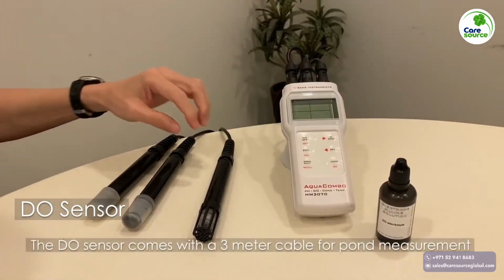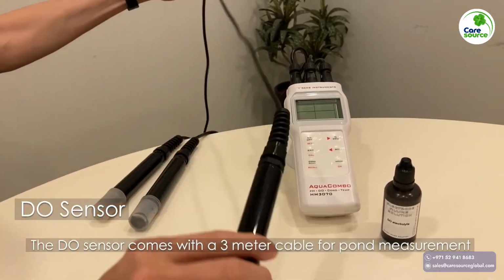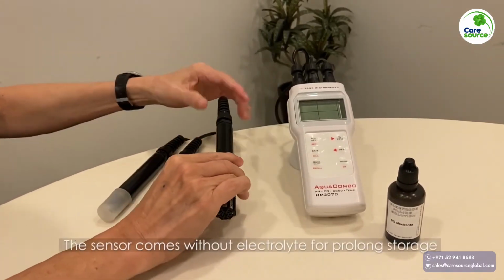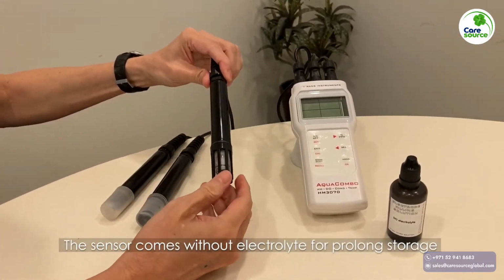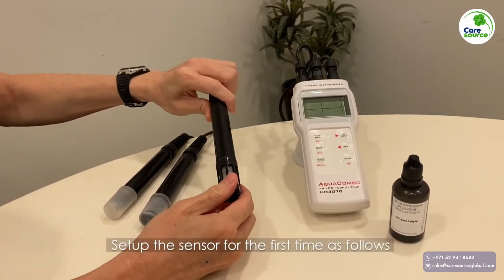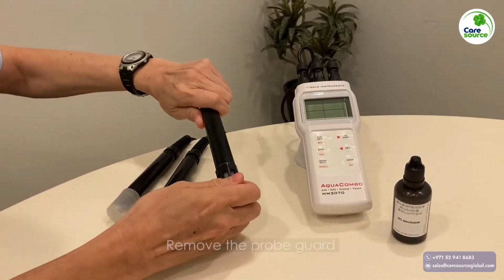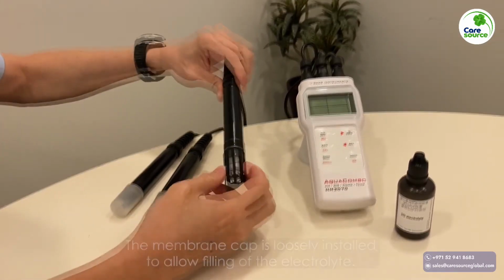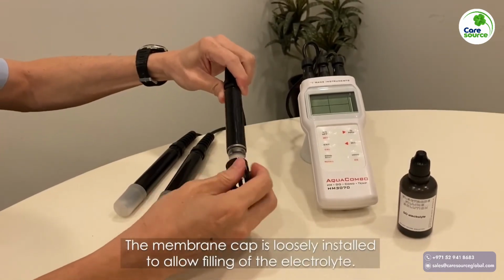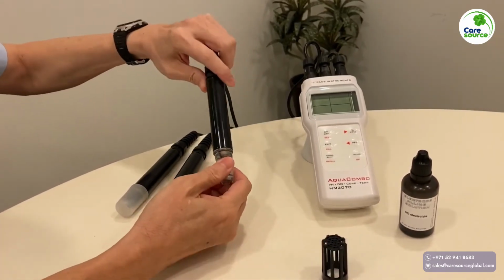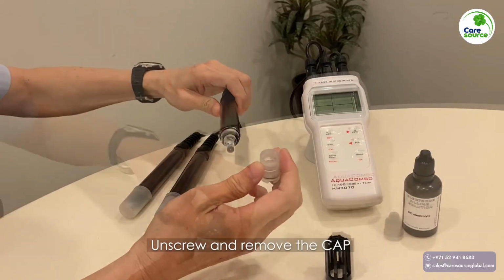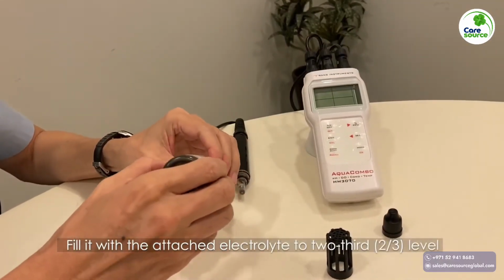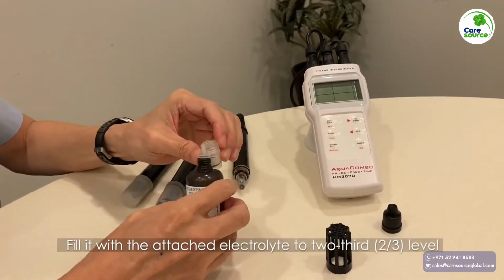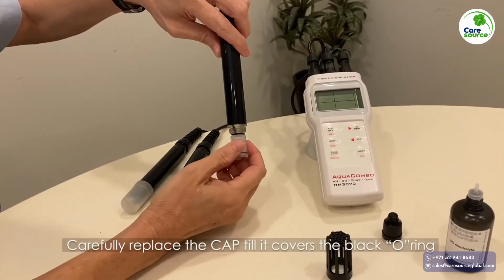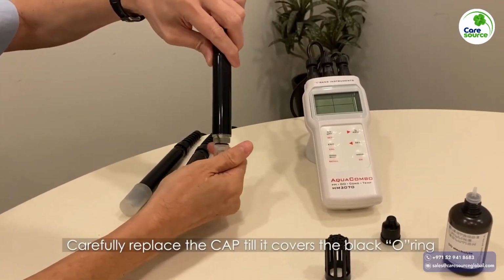The DO sensor comes with a 3 meter cable for pond measurement. The sensor comes without electrolyte for prolonged storage. Set up the sensor for the first time as follows. Remove the probe guard. The membrane cap is loosely installed to allow filling of the electrolyte. Unscrew and remove the cap. Fill it with the attached electrolyte to 2/3 of the level. Carefully replace the cap till it covers the black O-ring.